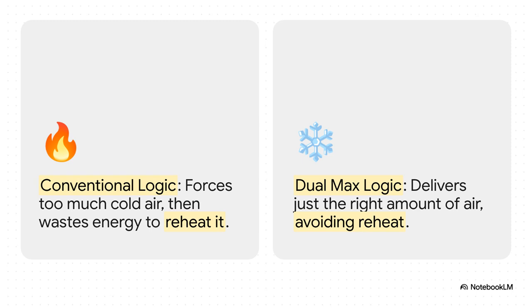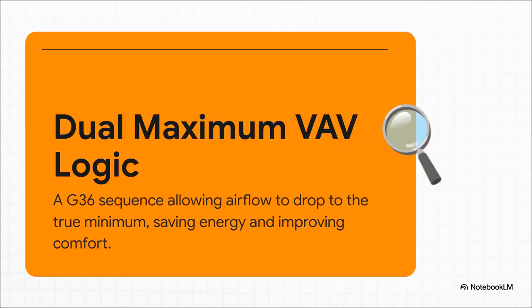The G36 logic is way smarter. It delivers only the tiny bit of cool air that's actually needed, so it never has to do that wasteful reheating. This smarter approach has a cool name: Dual Maximum VAV Logic. It's one of the secret weapons inside Guideline 36. All it really means is, instead of a dumb, fixed minimum airflow, the system is smart enough to let the airflow drop way down to what's truly needed for ventilation. The amount of energy you save on fans and heating is just enormous.